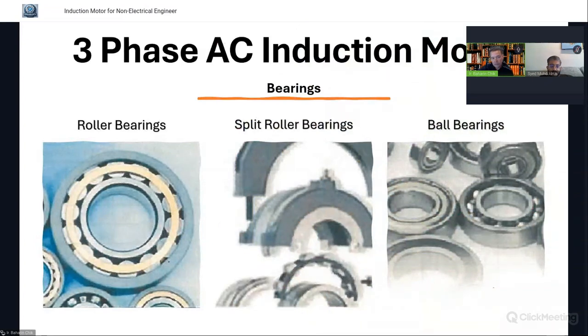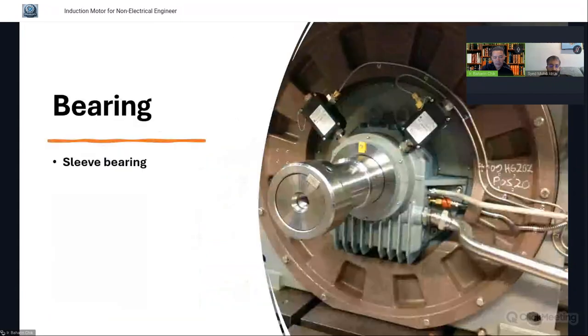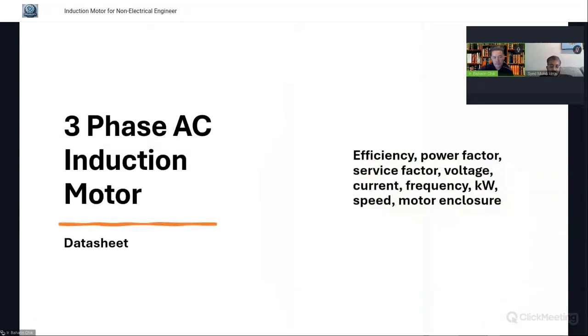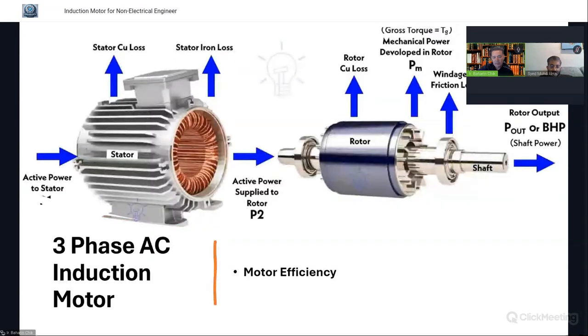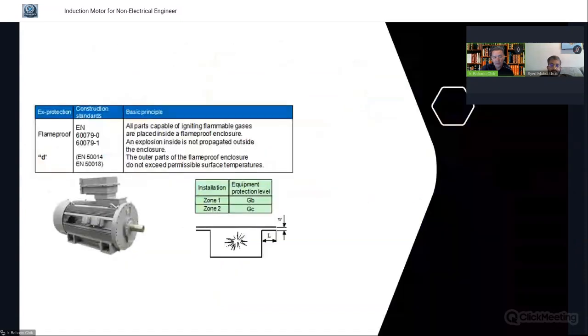And then for induction motors we also have three types of bearing: roller, ball, and sleeve bearing. In the next slide, this is the sleeve bearing for the HV motors. And also we need to look into the data sheets of the motors, see the efficiency, power factor, service factor, and voltage. And then for the efficiency, we need to remove the losses in terms of heat effectively using fans that are driven by the shaft of the motors or external fans, depending on the design.